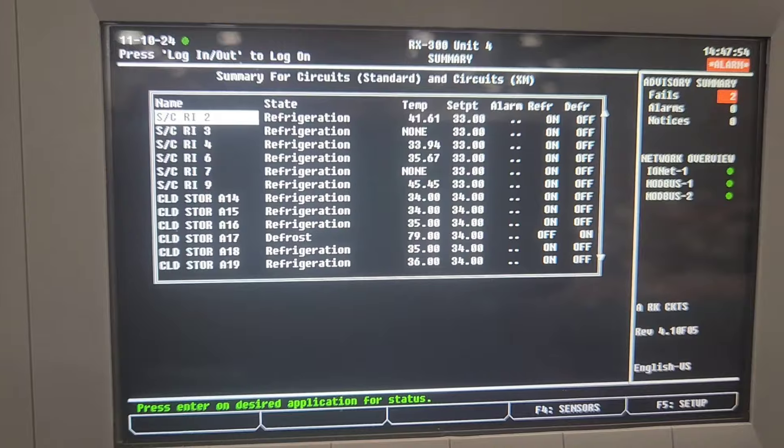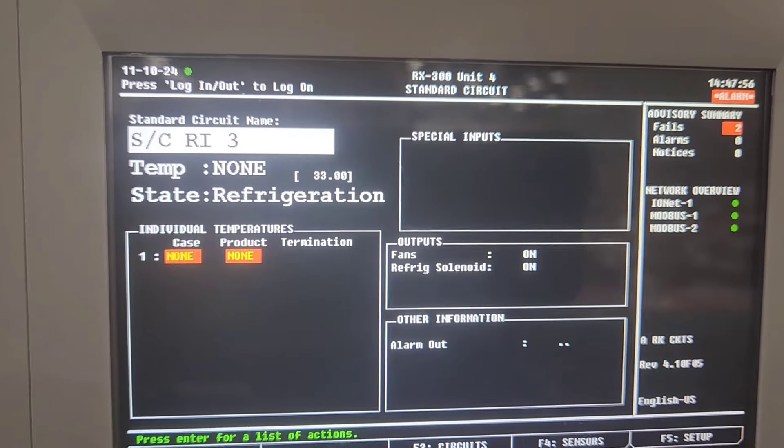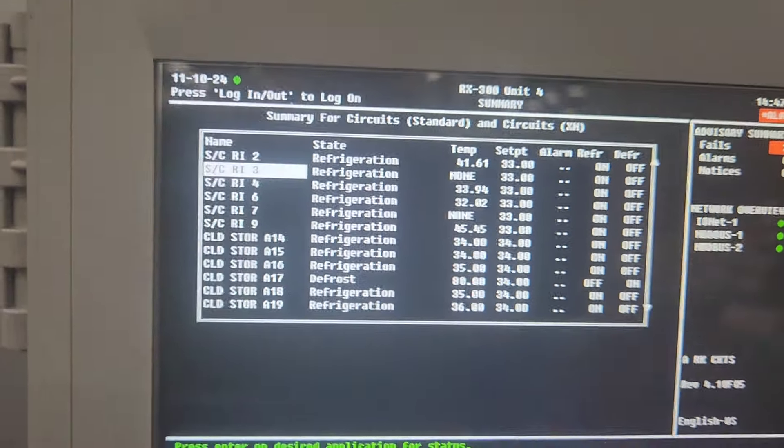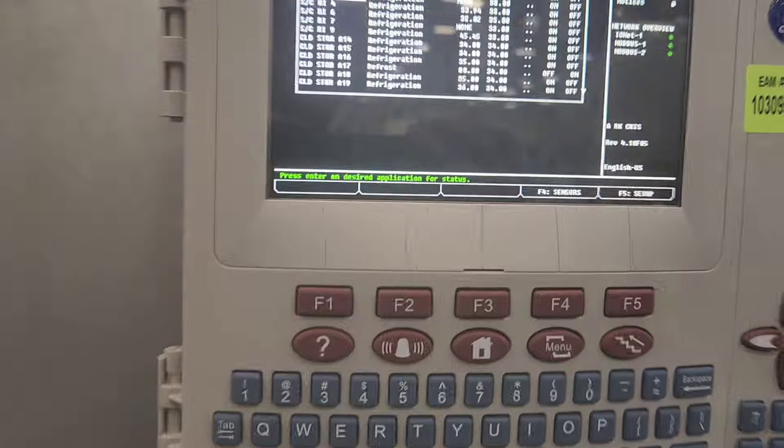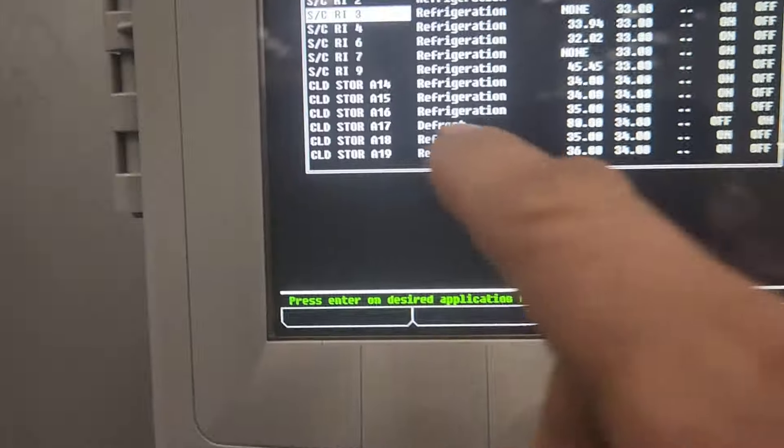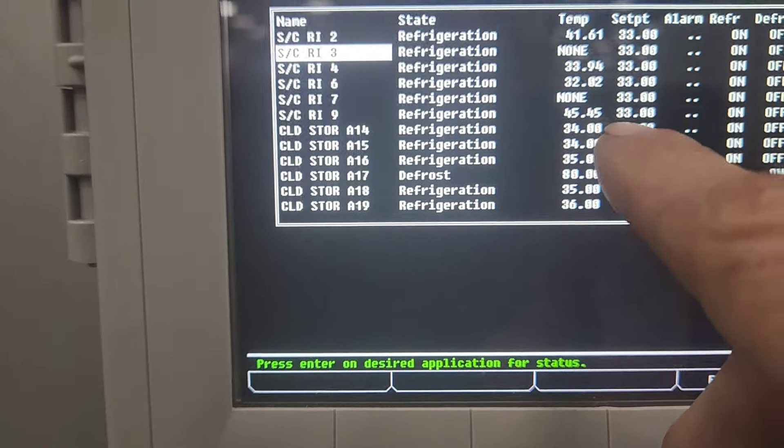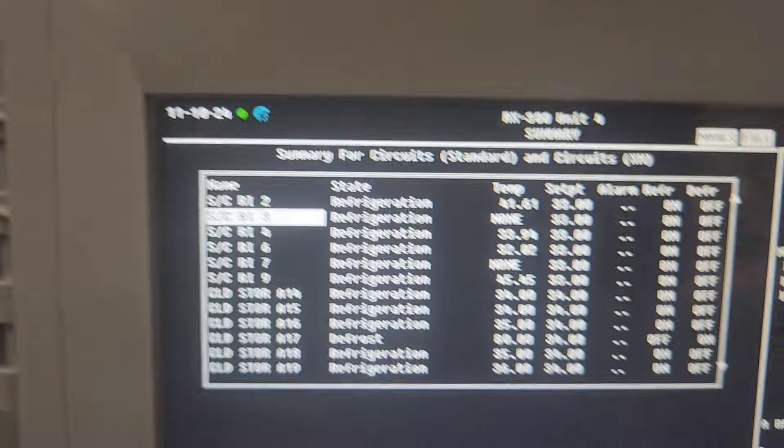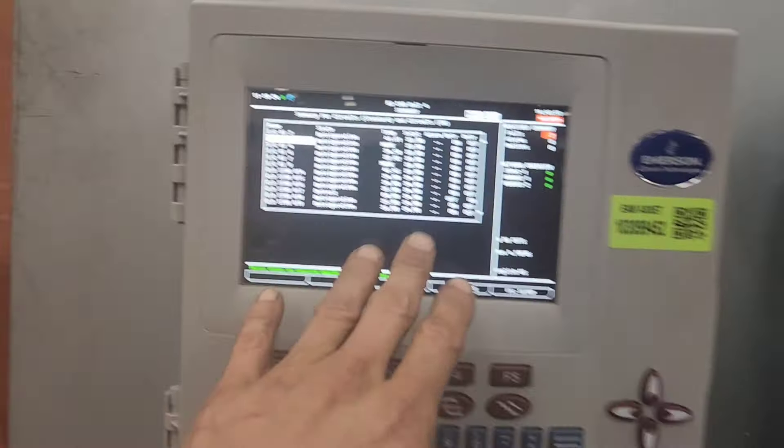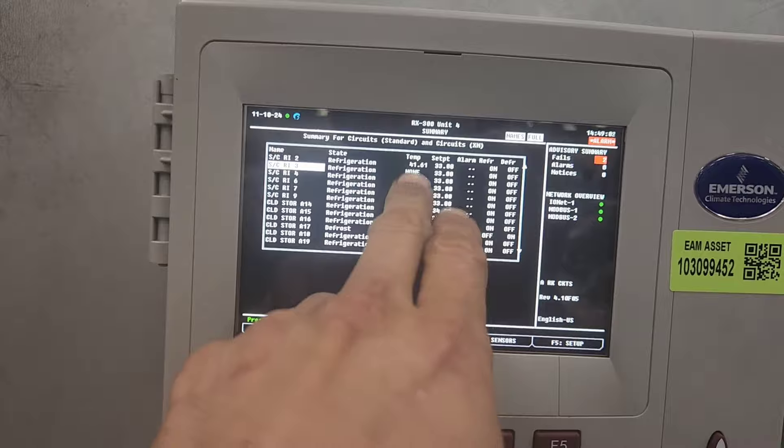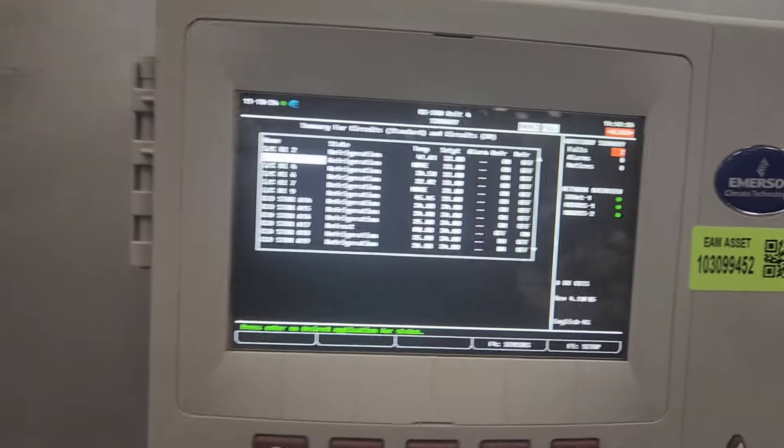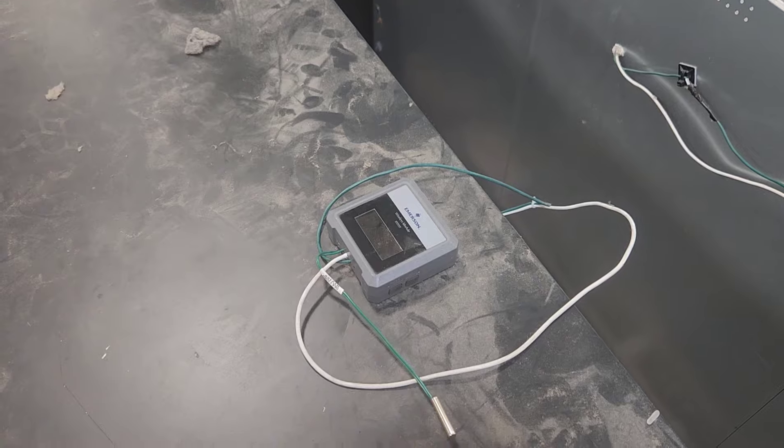I mean I could probably just leave it like this for now, because once I connect that back the alarm should be gone. You see right now we don't have a sensor on case nine because I have that one disconnected, but who cares. I'm just gonna leave it because I fixed the issue that they called us out for, the alarm that we had at 70 degrees. So I'll put number three back and that'll be it.